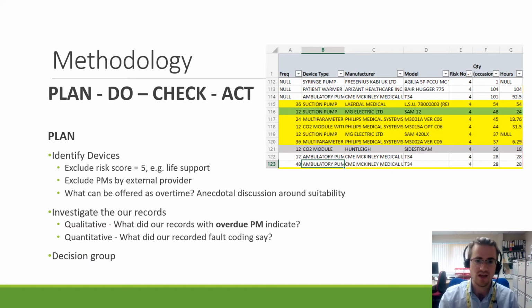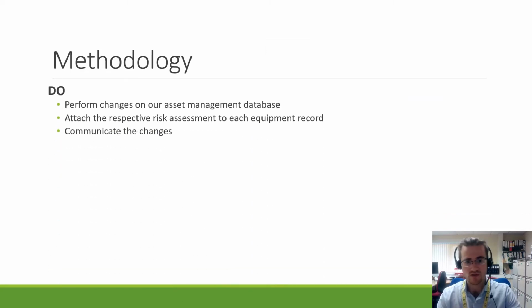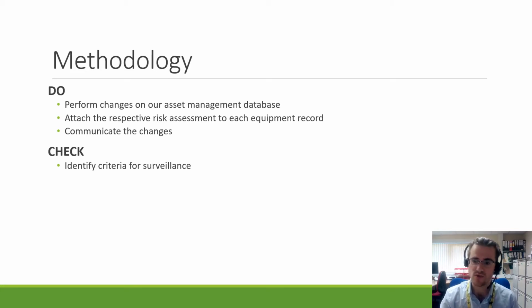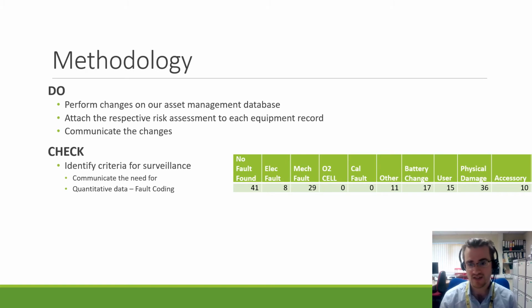We'd discuss in full. When we had decided to take it forward, we'd obviously go on to the do phase, where we would perform changes on our asset management database. We communicate those changes to the technical staff and, where necessary, clinical staff. We'd attach the risk assessments to the equipment record so that everything's in a traceable manner, it's all auditable, and we know which equipment's been affected. And then onto the check phase, so we also identified surveillance criteria, which was very heavily reliant on quantitative data of our fault coding, where we would identify what was an important code to use as surveillance data.